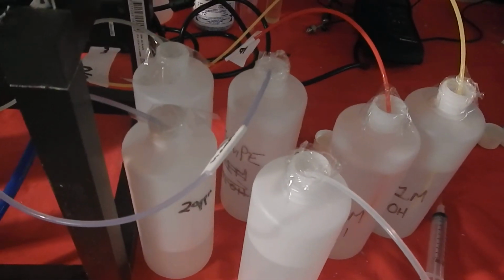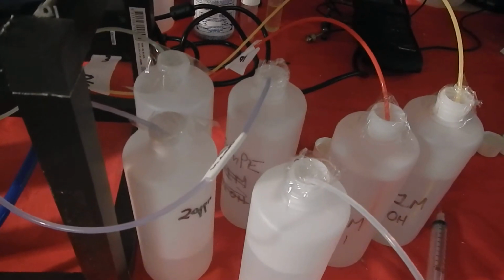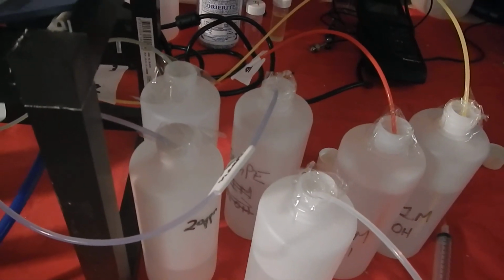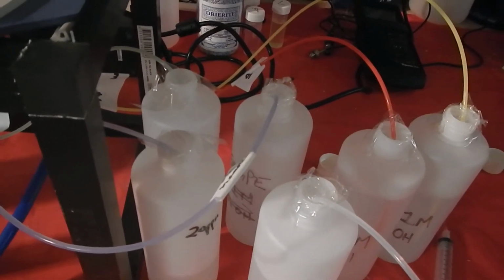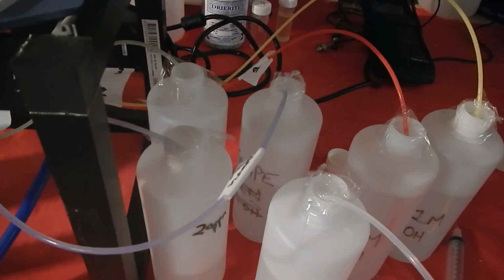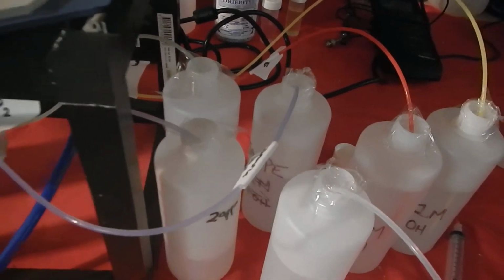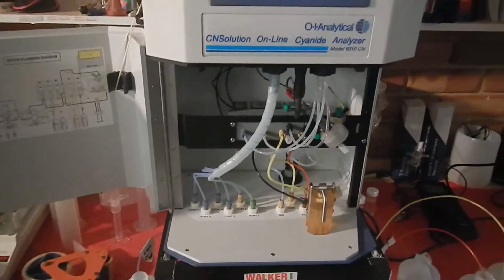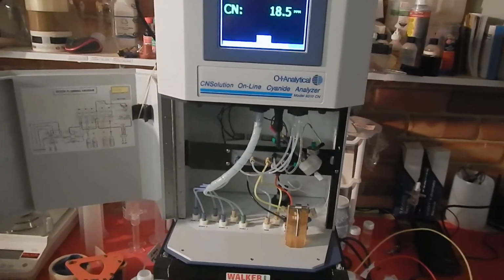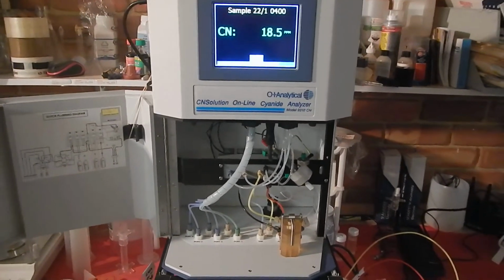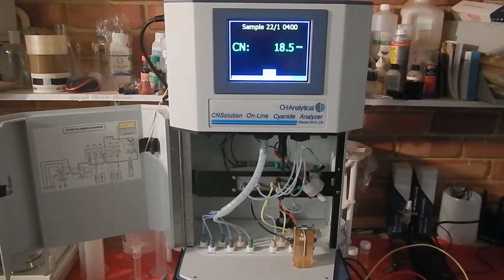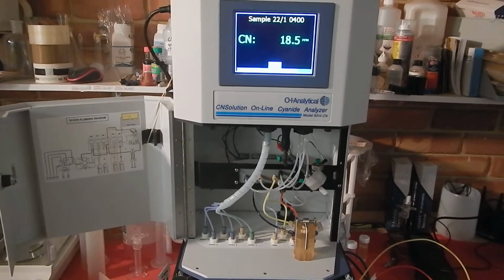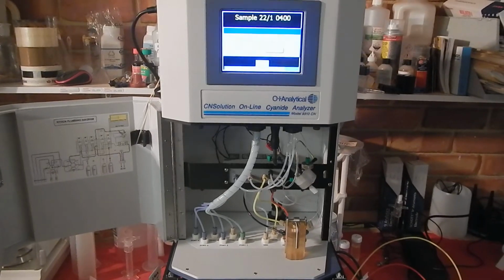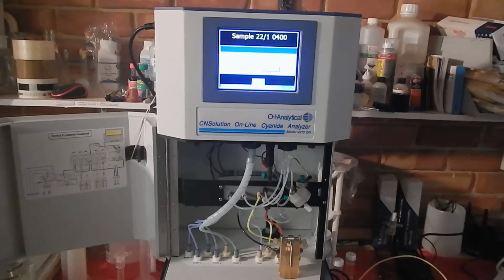Your standards, depending on the level, would need to be changed regularly. If they're very low levels, probably daily. If they're high levels in hundreds of ppm, possibly weekly. Those are things that need to be worked out on each site. But as it stands, the instrument is very, very easy to use, very operator friendly, with a lot of the features of the laboratory instruments, which is well regarded in the field. Interferences are minimal, and it has ease of operation.